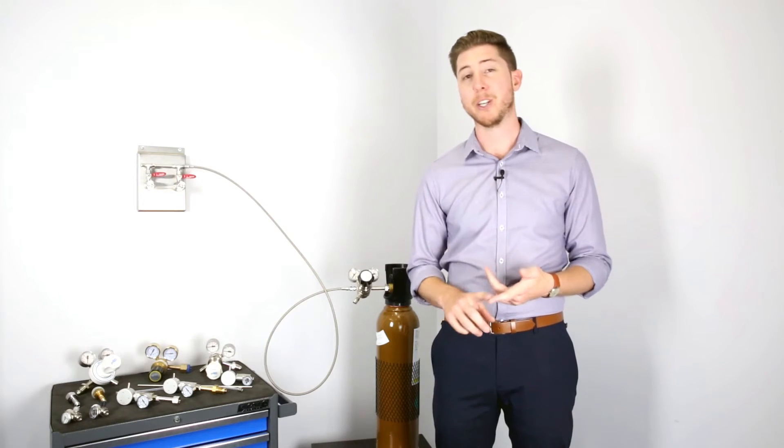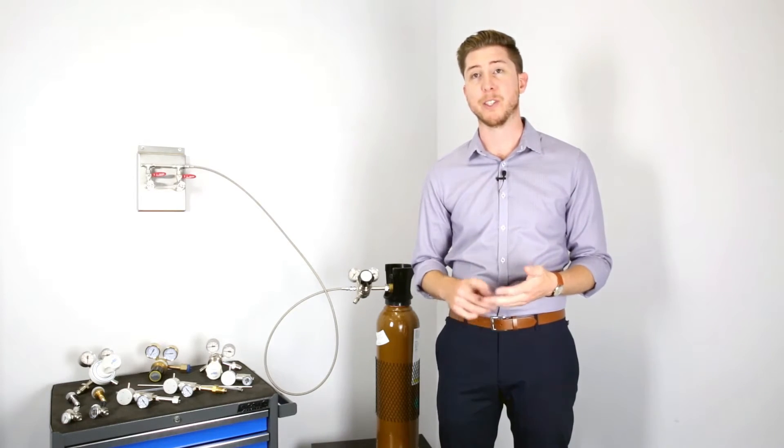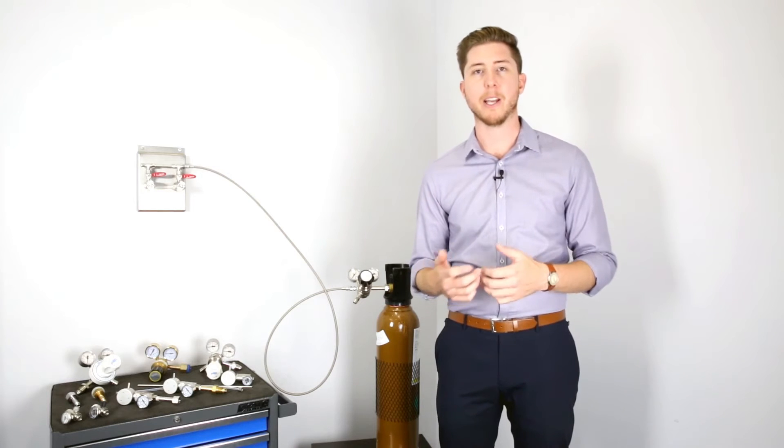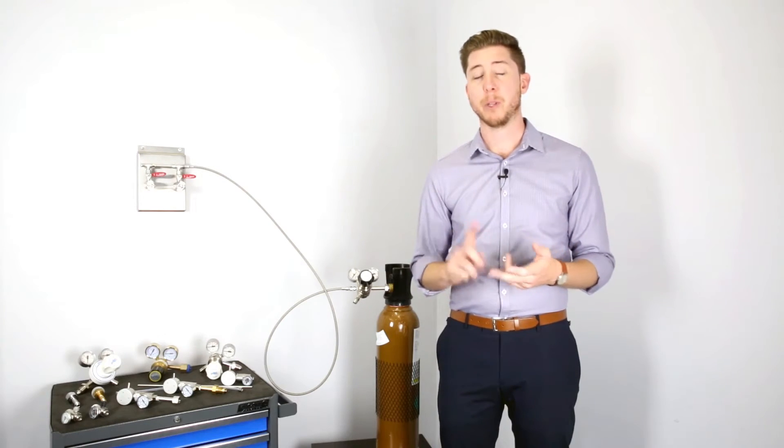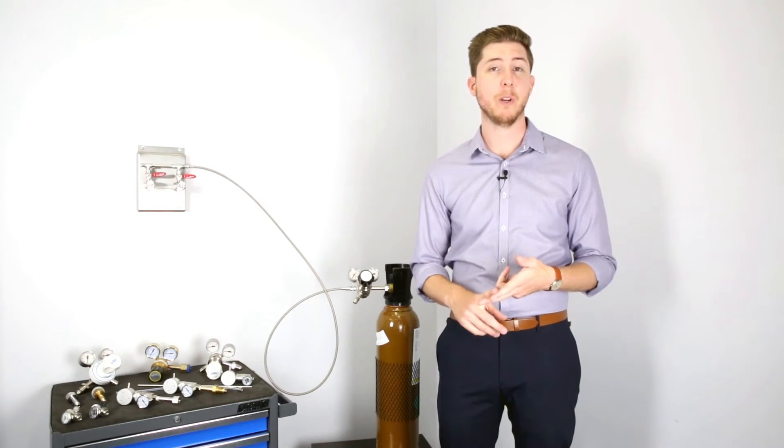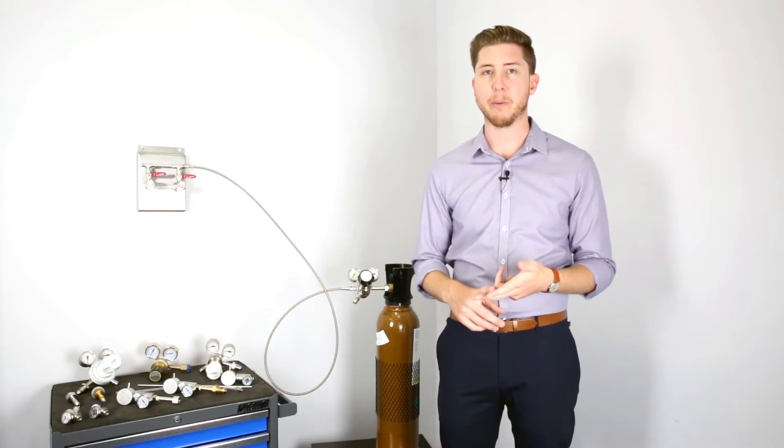Non-corrosive gases include CO, CO2, nitrogen, and zero air. These gases can use brass or nickel-plated brass and standard Tygon tubing. Please remember that nickel-plated brass is suitable for H2S and SO2 in concentrations below 50 ppm.